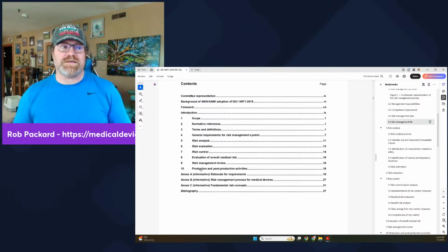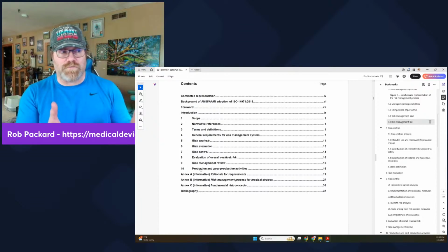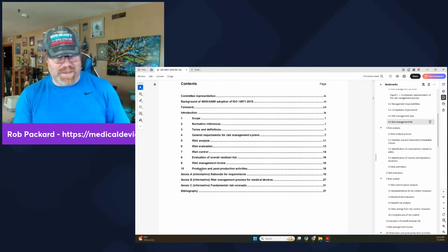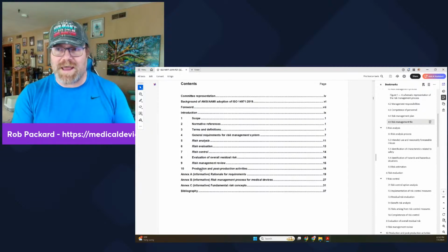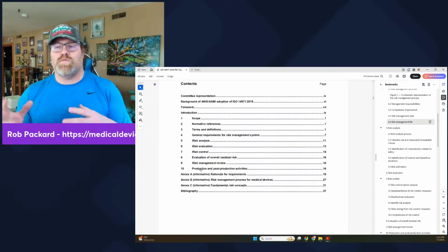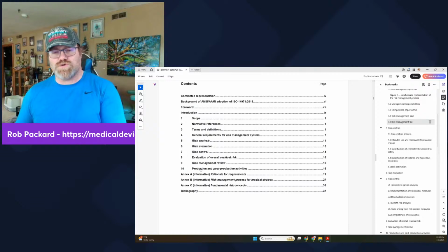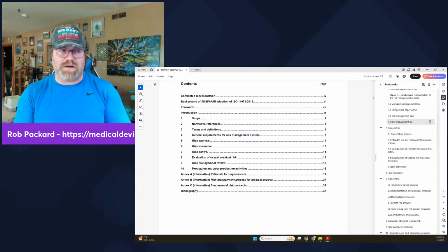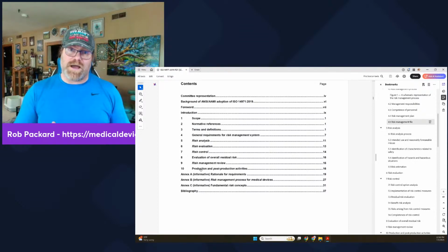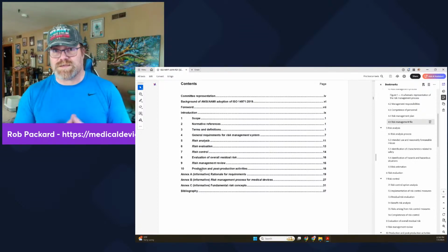The V&V testing is your evaluation of overall residual risk. It's verifying that the risk controls are complete and adequate. And we say, okay, these are the residual risks. We're going to list them in our instruction for use or user manuals, say what those residual risks are. We say whether they're acceptable or not. We could do a benefit risk analysis. I recommend doing a benefit risk analysis.